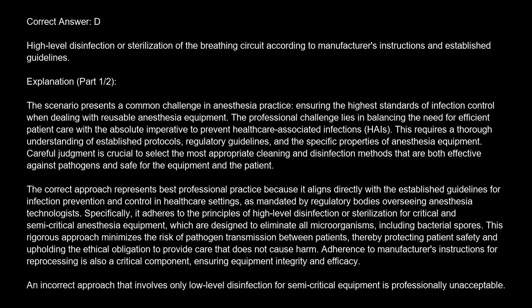The correct answer is D. High-level disinfection or sterilization of the breathing circuit according to manufacturer's instructions and established guidelines. Explanation. The scenario presents a common challenge in anesthesia practice, ensuring the highest standards of infection control when dealing with reusable anesthesia equipment. The professional challenge lies in balancing the need for efficient patient care with the absolute imperative to prevent healthcare-associated infections. This requires a thorough understanding of established protocols, regulatory guidelines, and the specific properties of anesthesia equipment.